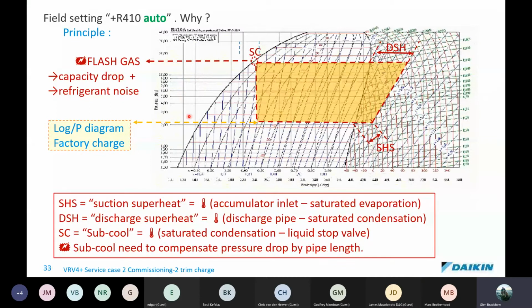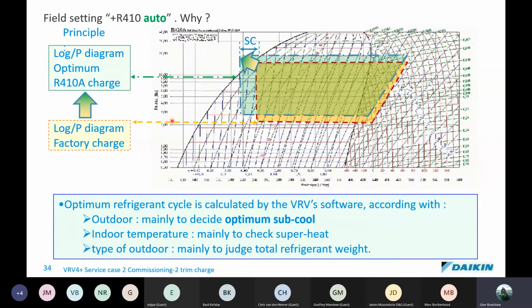When the system is charging like this, as the refrigerant goes into the system, it moves the pressure enthalpy diagram, and we see some subcooling taking place. We still have suction superheat and discharge superheat, and you can see it's critical that we get subcooling. I always remember as an apprentice, my journeyman used to push it home that you have to have good quality liquid in order for a refrigeration system to operate. That's the part of our air conditioning system that we need to concentrate on. The quality of your liquid is critical, and that is what the system is looking at while charging.